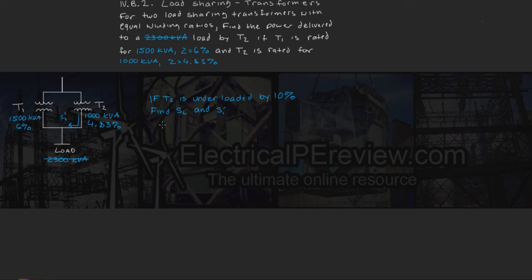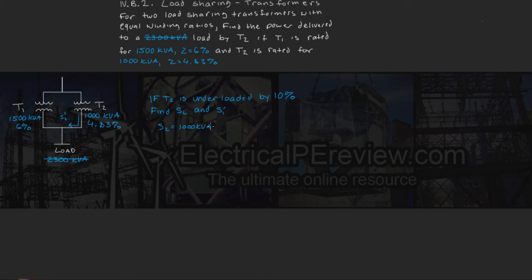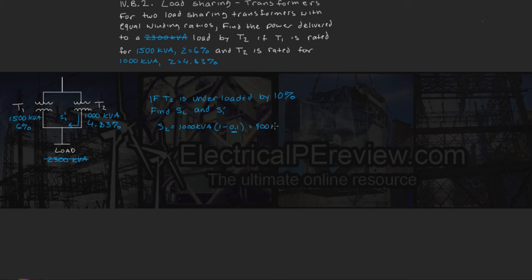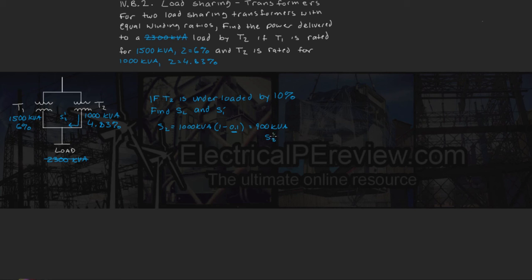Well, we know that our S2 rating is 1000 kVA. We can multiply this by 1 minus 0.1 for our 10%. This comes out to be 900 kVA, which is our new S2 prime or our contribution from transformer 2 flowing to the load right here.